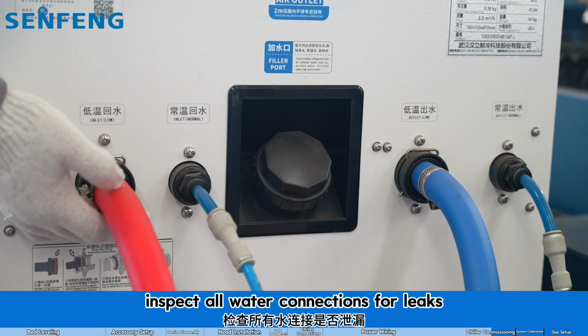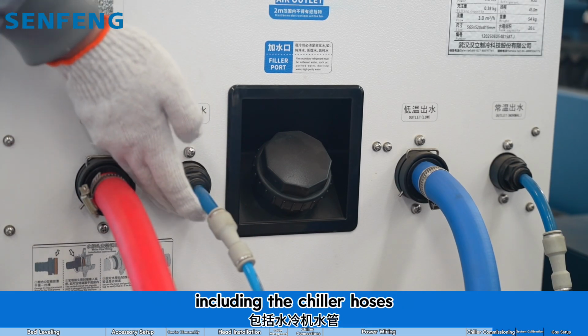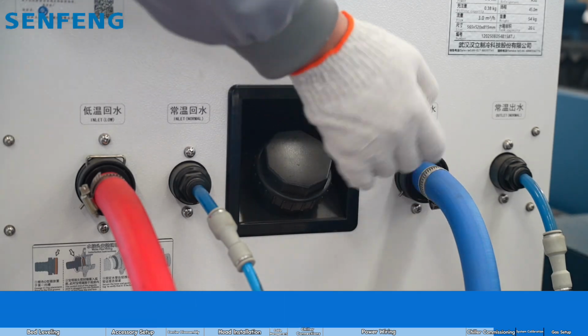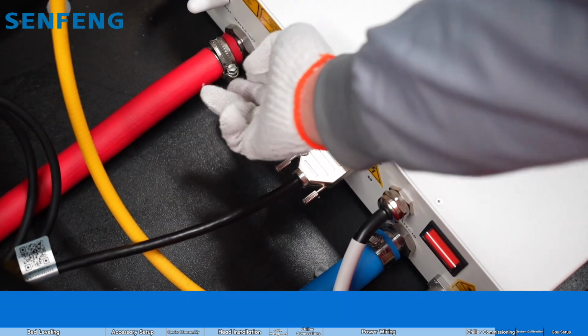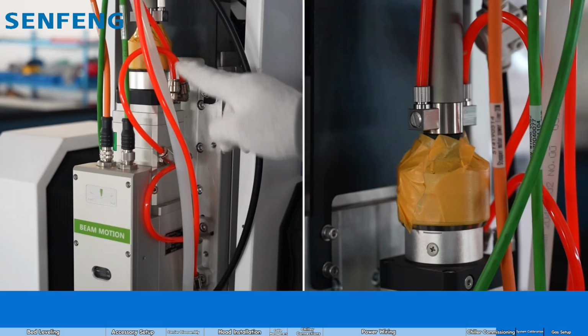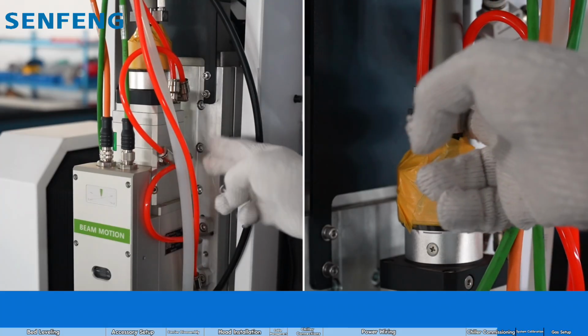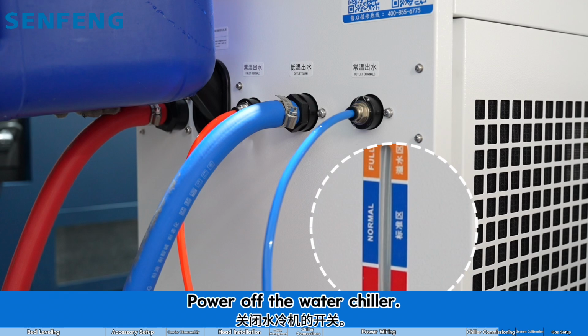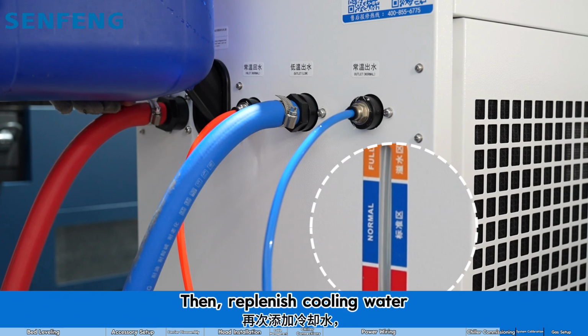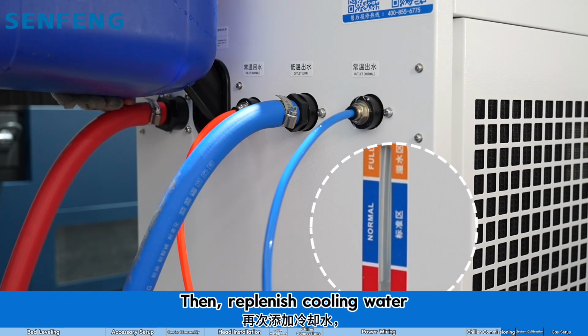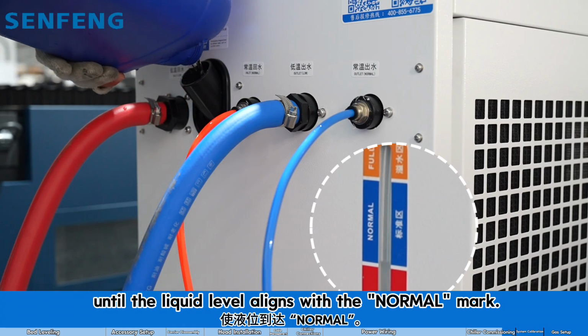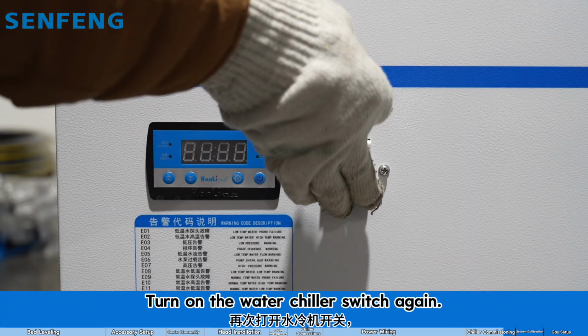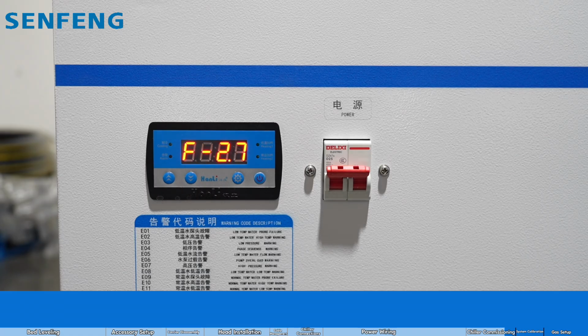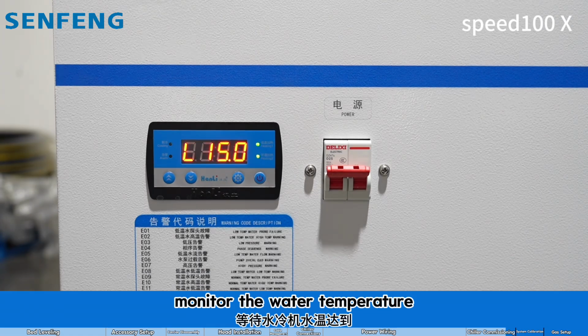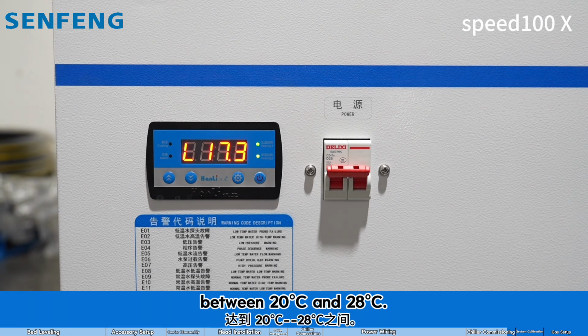Inspect all water connections for leaks, including the chiller hoses, laser source cooling lines, and the laser head cooling circuit. Power off the water chiller. Then, replenish cooling water until the liquid level aligns with the normal mark. Turn on the water chiller switch again. Monitor the water temperature and wait for it to stabilize between 20 degrees Celsius and 28 degrees Celsius.